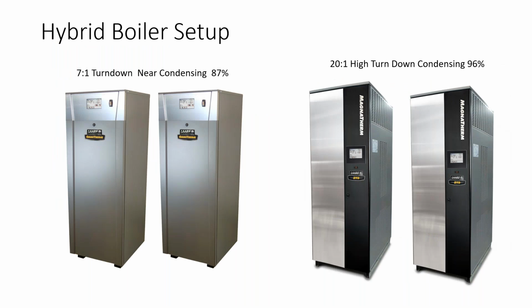So the hybrid boiler setup. So this is just a single slide, and it's just to give you an idea. We've been working hard on coming up with something that will give you the best cost and efficiency standards in your building designs. So a lot of times in the dead of winter where we'll get a 20-degree day, you're not going to condense no matter what you do, because you're putting out the highest heat, highest temperatures. You're running that system at the highest rates. Your return temperatures are way too high for condensing. So why not use a combined system or a hybrid boiler plant where you have near condensing product as well as full condensing product? It gives you the best of both worlds.